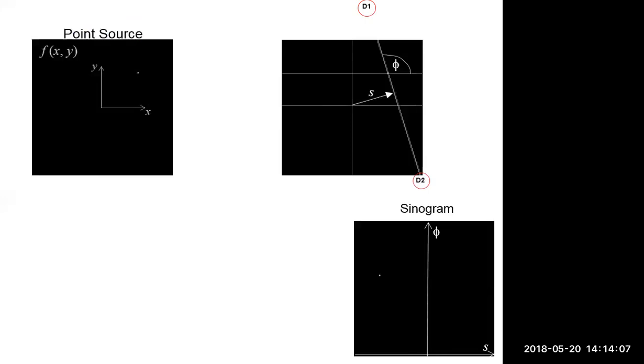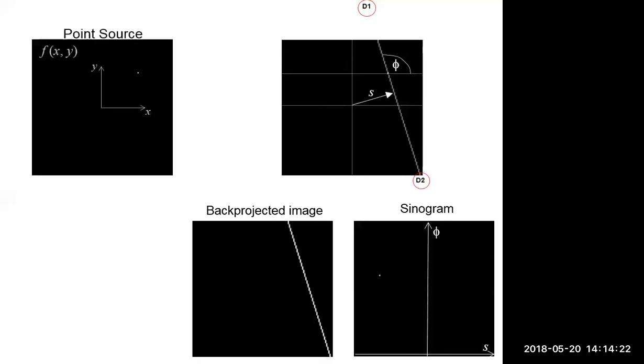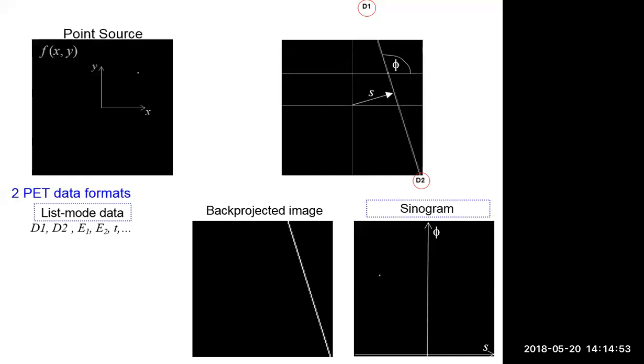The sinogram is discretized — with discretization in the radial S direction and in the viewing angle phi direction. Alternatively, you could back-project into an empty array, or record the data in list-mode format: 'I detected an event on detectors D1 and D2,' and you can also record the energy of each photon and the time difference. List-mode data is very flexible — you have many attributes per event. Today I'll focus on the sinogram data format in 2D for simplicity.